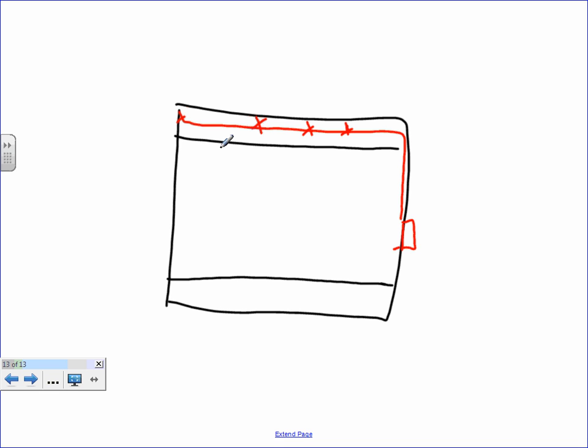Your detector spacing is 900 square feet. And NFPA 72 reduces it, if you go on, is it 60 air changes an hour? Then you reduce it from roughly 30 feet on center, typically, to 9 feet. So every 9 feet you have to have a smoke detector. So we're cross zoning this.